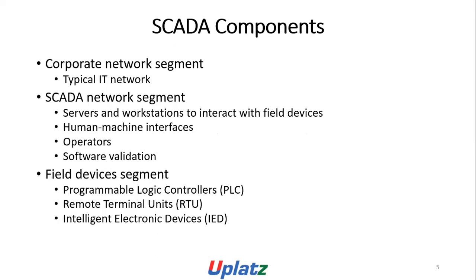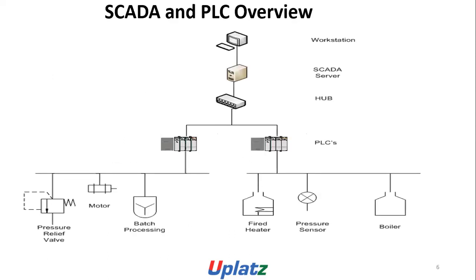SCADA components: the corporate network segment, a typical IT network; the SCADA network segment, with servers and workstations to interact with field devices, human machine interfaces, operators, and software validation; and field device segments, with programmable logic controllers (PLC), remote terminal units, and intelligent electronic devices. So we have the workstations, SCADA server and the hub, PLCs, and batch processing, motor, pressure relief valve, fired heaters, pressure sensors, boilers.